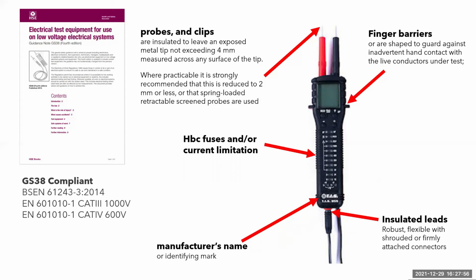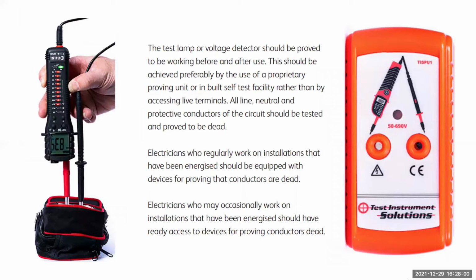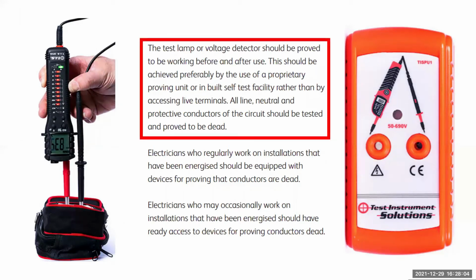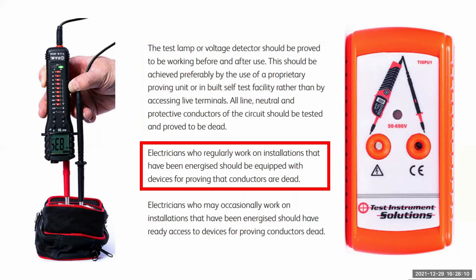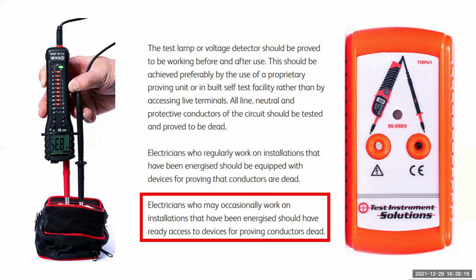The guidance set out by Best Practice Guide 2, Issue 3, is that you should preferably test your voltage indicator safely on a dedicated proving unit like this one, rather than accessing live terminals. It also suggests that electricians who work on installations or regularly work on installations that have been energized should have one, and even those that only occasionally work on installations should have one too.